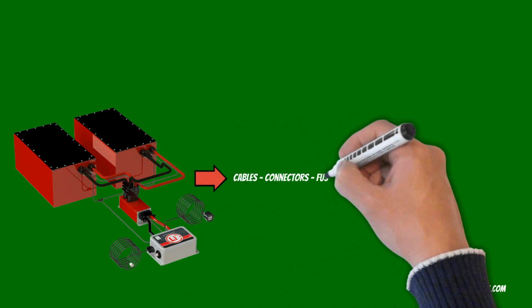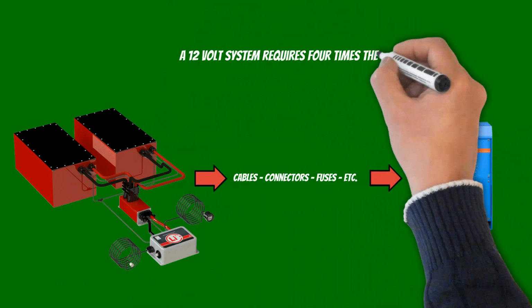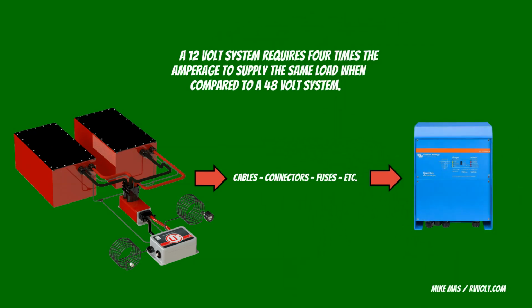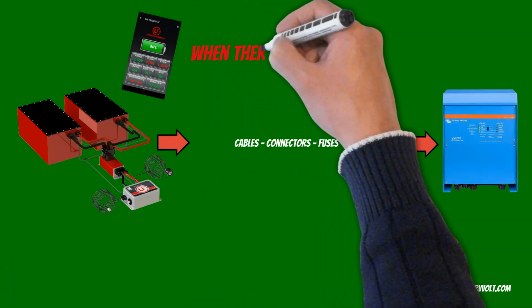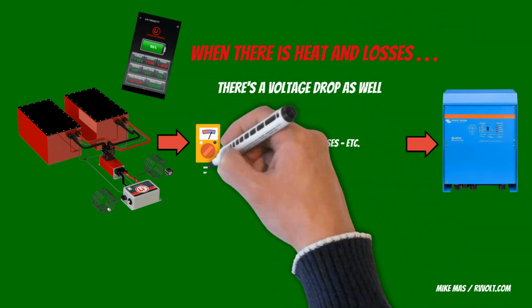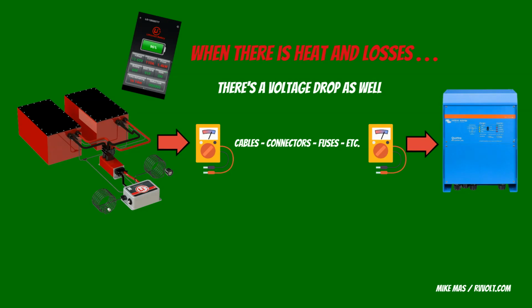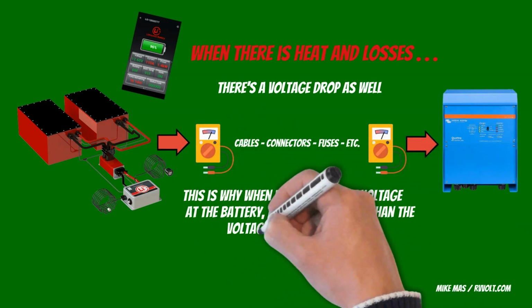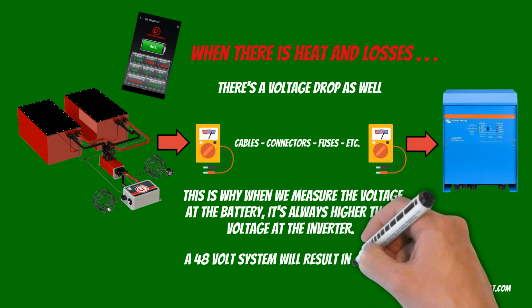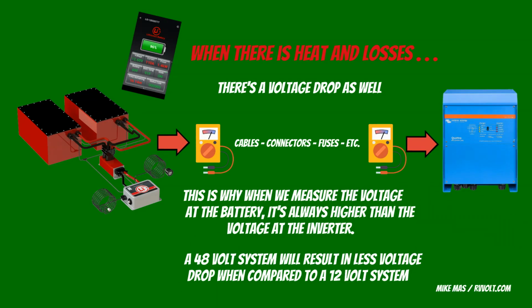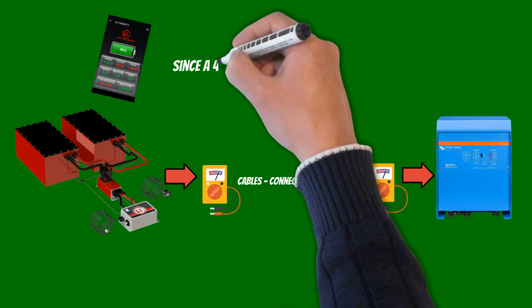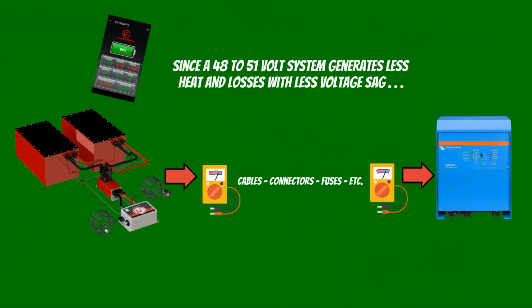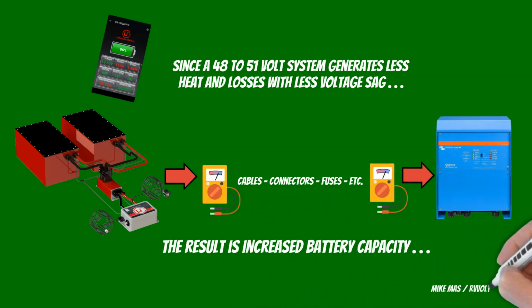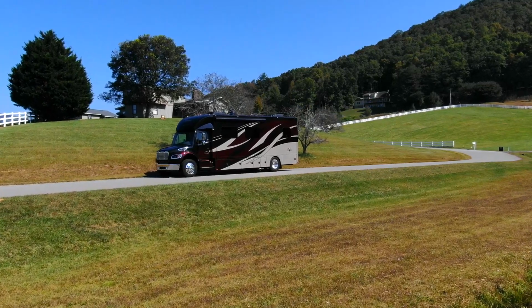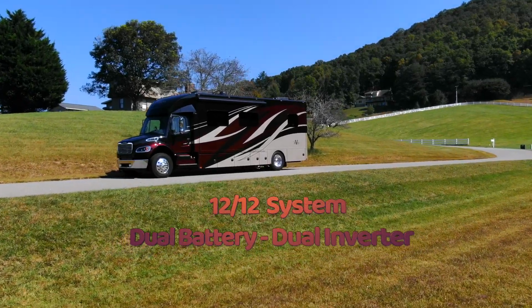As this comparison shows, a 12-volt system requires 4 times the amperage to supply the same load when compared to a 48-volt system. When there is heat and losses, there's a voltage drop as well. This is why when we measure the voltage at the battery, it's always higher than the voltage at the inverter. For this reason, a 48-volt system will result in less voltage drop when compared to a 12-volt system. In conclusion, since a 48 to 51-volt system generates less heat and losses with less voltage sag, the result is increased battery capacity.